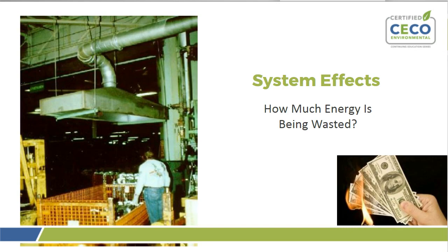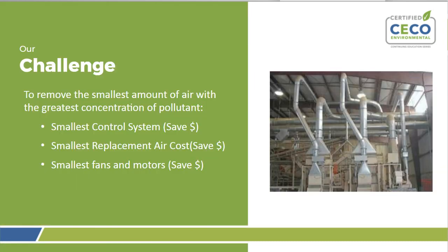Okay, now we're going to talk about system effects, and they must be considered. A well-designed and placed hood will save money as opposed to wasting energy and wasting money. When initiating an industrial ventilation design, the focus and challenge should be to remove the smallest amount of air with the greatest concentration of pollutants. If we are successful here, then we will have the smallest control system, and a smaller system is going to cost less to install, and we will invariably then have smaller fans and motors, and that system then would cost less to operate. And the hoods provide the first opportunity in the ventilation system to reduce airflow rates and meet objectives to reduce employee exposure.